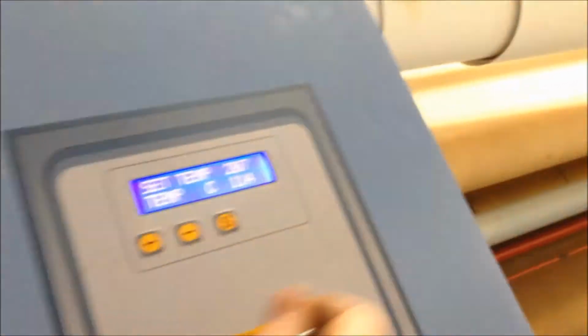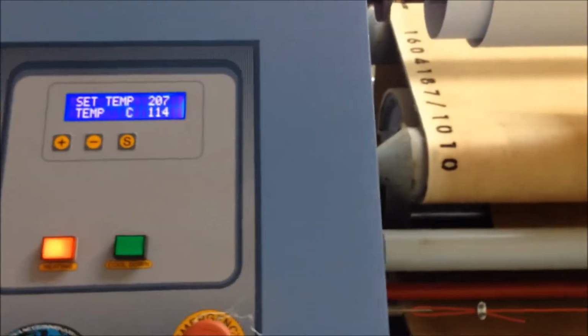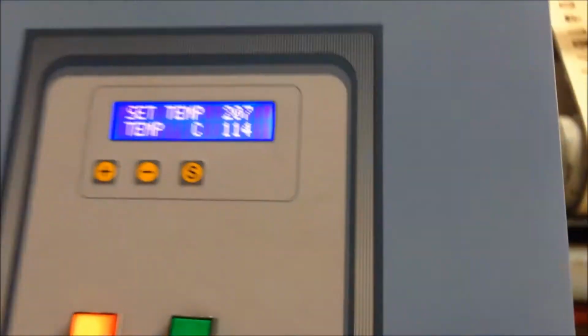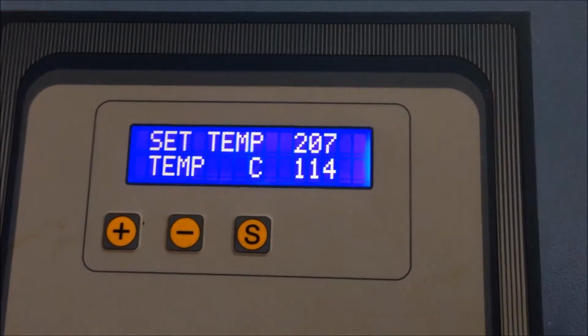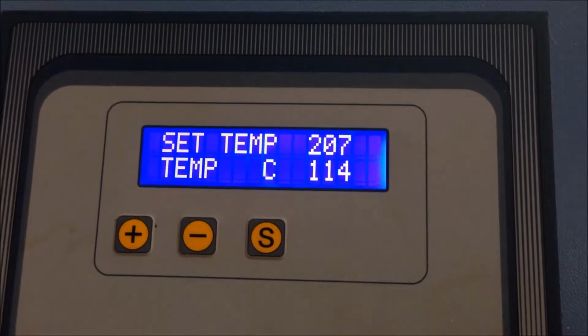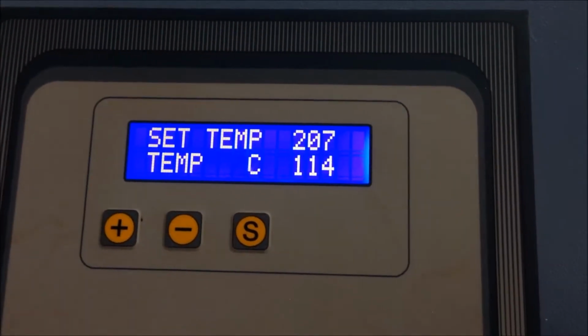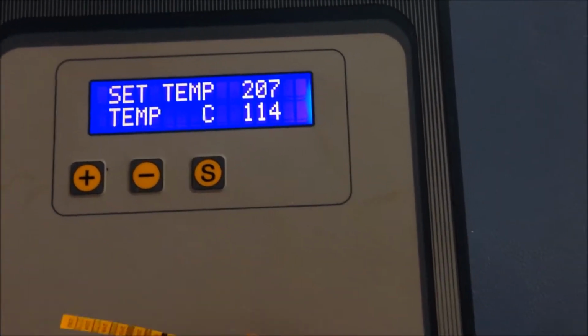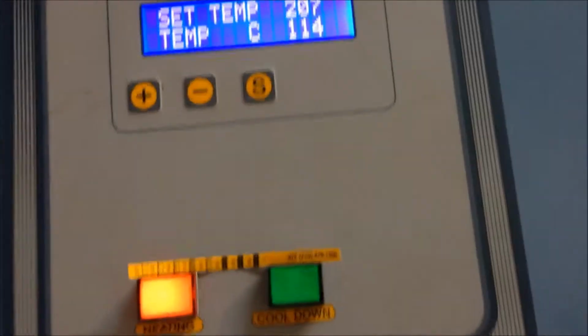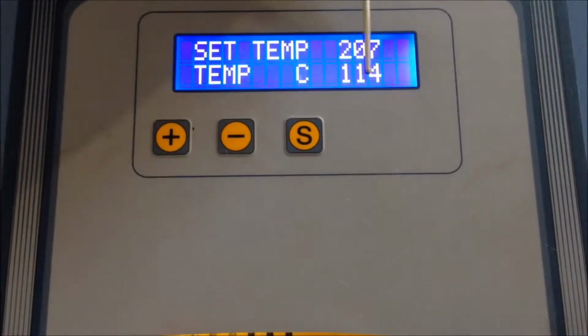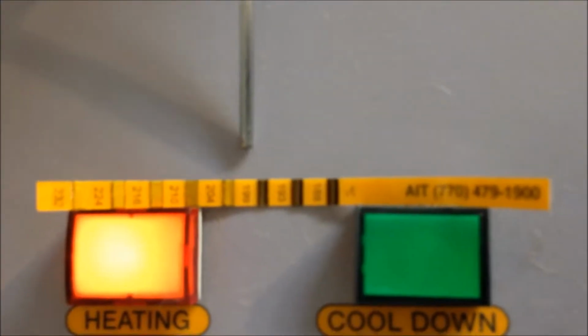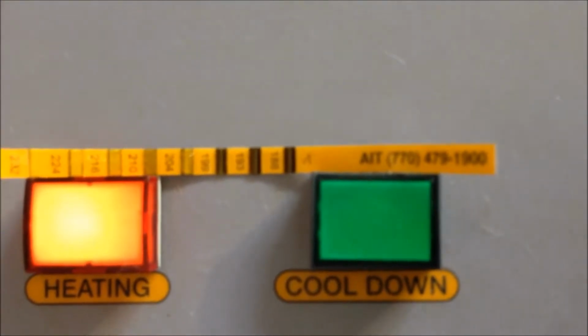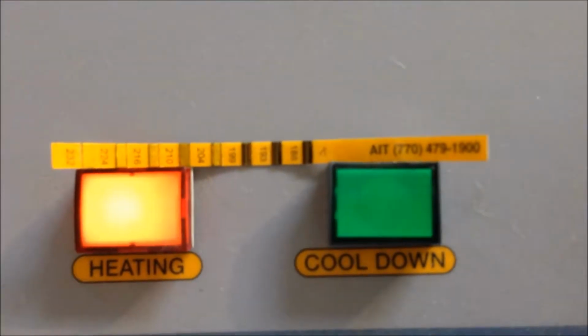So we'll come around to the front and we'll look at what we've got here. Our temperature is reading 114. Our set point is 207. Now, once this reaches 207, obviously my temp strip, I should run this through to see what my temperature is. So, at a set point of 207, this says 199. Let me focus on that. So our temp strip is saying 199.